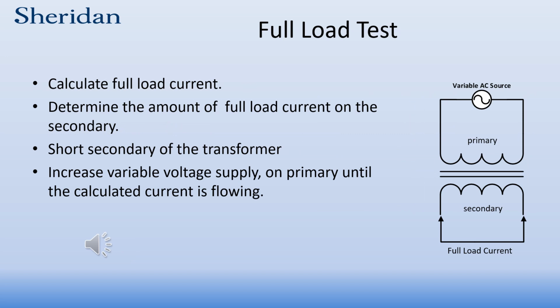First of all, what we need to do is calculate the full load current, to determine the full load current on the secondary of the transformer. Then what we do is short the secondary of the transformer. Now you have to be very careful not to just apply rated voltage to the primary. What you'll end up doing is vaporizing the conductor you put on as a short, and you can cause yourself great injury in doing so. So you have to be very careful doing these types of tests. You increase the supply on the primary until that calculated full load current is flowing in the secondary.